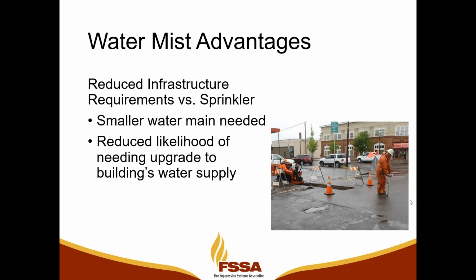Water mist also reduces the likelihood that we're going to have to upgrade a building's water supply. And that's because we're using 50% to 90% less water than we would with a traditional sprinkler system. So we can have a smaller water supply to our building. And we've experienced this in the real world.